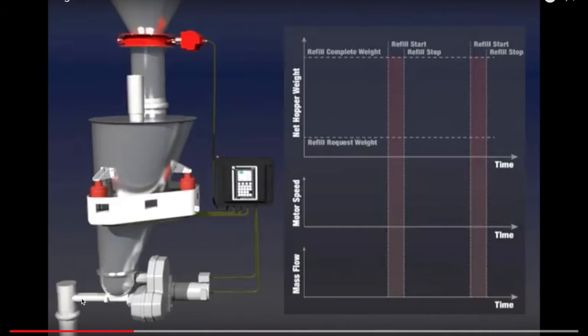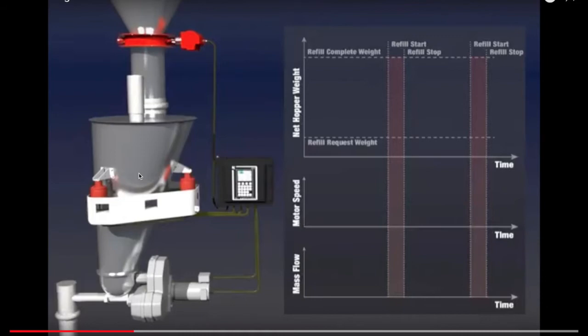The way it knows what speed to be turning the screws is based off of the controller. The controller is constantly looking at the weight of the surge tank, and it's looking at how much it is losing per time. So if in a given minute, if it loses 10 pounds, then the flow rate is 10 pounds per minute. And it will regulate the screw speed so that it makes the flow rate equal to what is the targeted amount of flow.